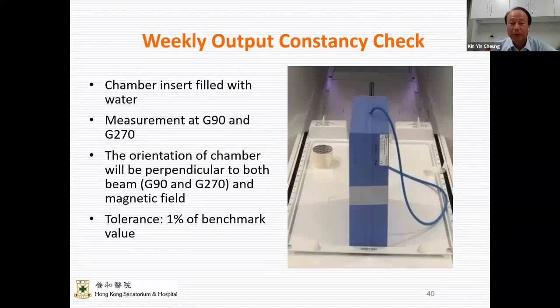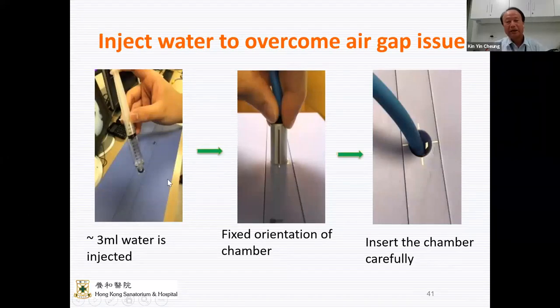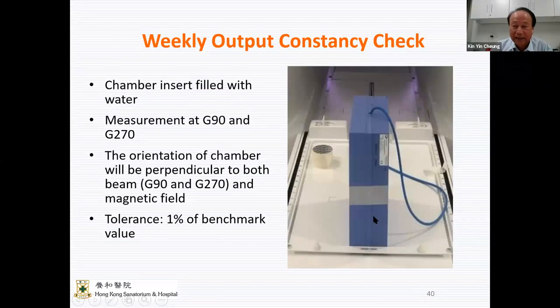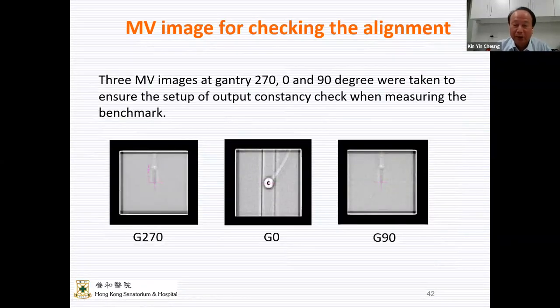Now, in the weekly output monitor, we do it in a more stringent way. We put the chamber vertical so that we can put water into the chamber insert, so that there is no air gap between the chamber and the phantom. And we put it along the center so that the chamber is near the isocenter. And we make exposures at 270 degrees and also 90 degrees so that the beam is normal to the chamber. And we also use the MV imager to check the location of the chamber so that it's exactly the same location every time.